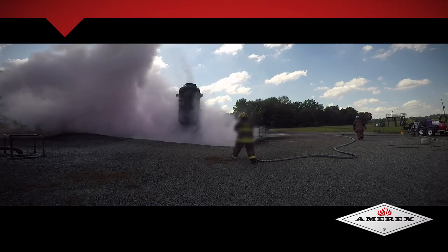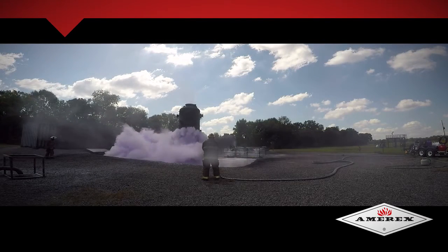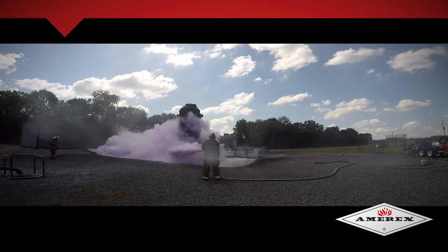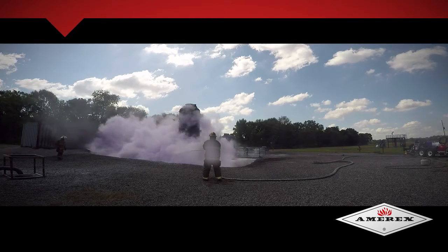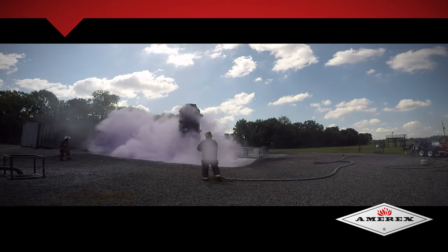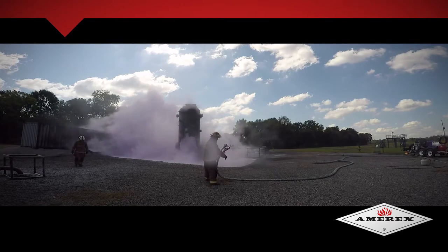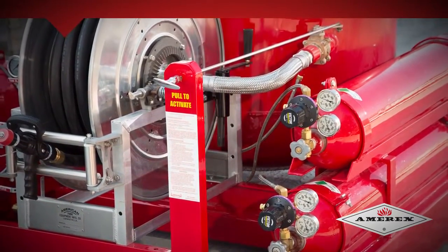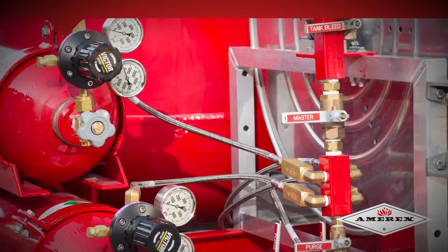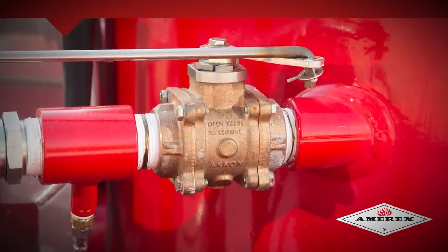Individual discharge valves to each hose reel on the skid unit allow either hose reel to be actuated without charging the hose reel not in use. Hose reels located in remote locations can also be actuated independent of the other reels in the system. All dry chemical and powder systems accommodate single-person manual operation or available automatic capabilities. Amerex Dry Chemical Systems utilize a corrosive-resistant protective process, and all dry chemical systems are assembled with stainless steel, brass, and bronze hardware.